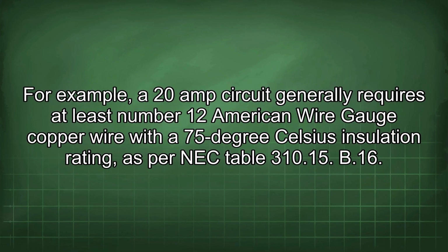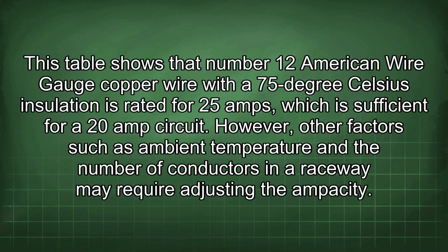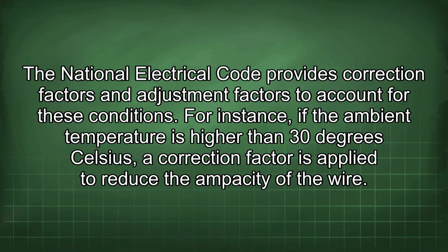For example, a 20 amp circuit generally requires at least number 12 American wire gauge copper wire with a 75°C insulation rating as per NEC Table 310.15(B)(16). This table shows that number 12 American wire gauge copper wire with a 75°C insulation is rated for 25 amps, which is sufficient for a 20 amp circuit. However, other factors such as ambient temperature and the number of conductors in a raceway may require adjusting the ampacity. The National Electrical Code provides correction factors and adjustment factors to account for these conditions.